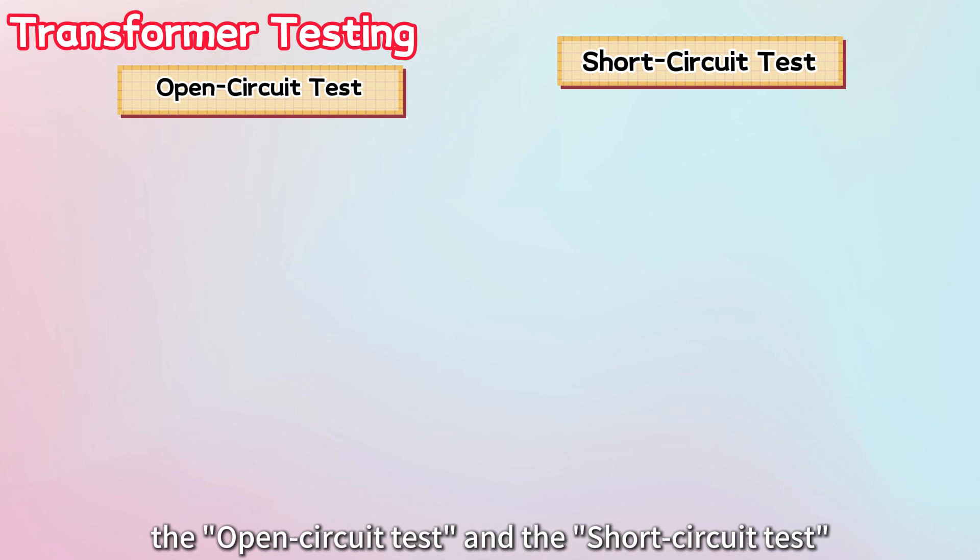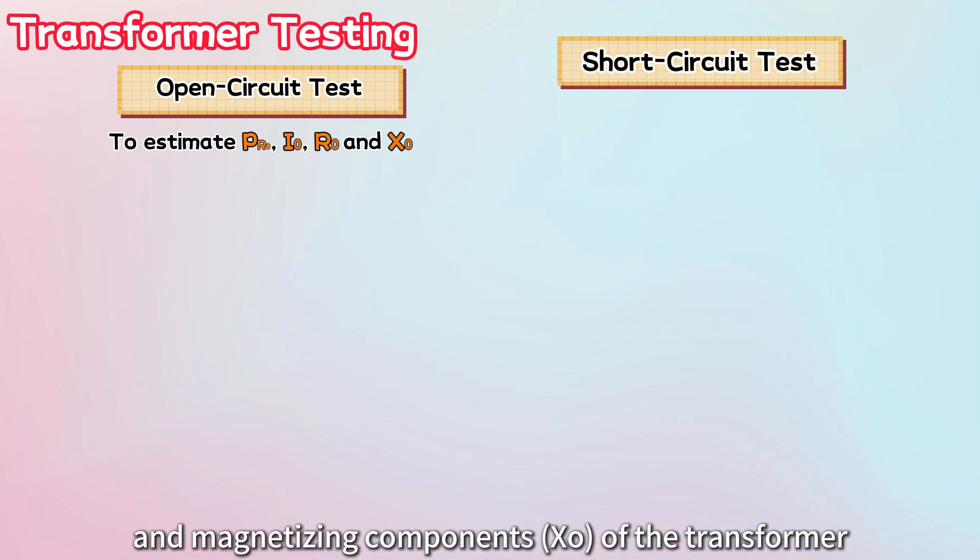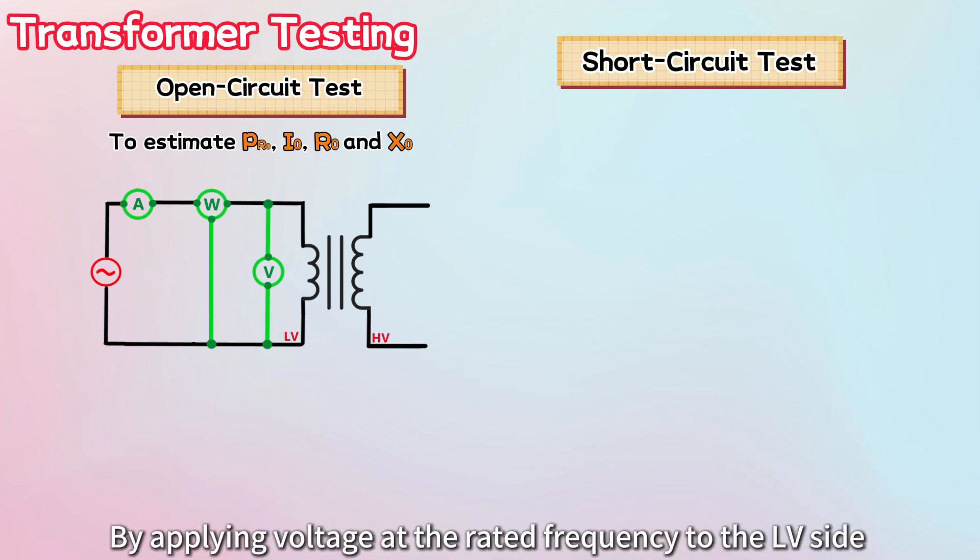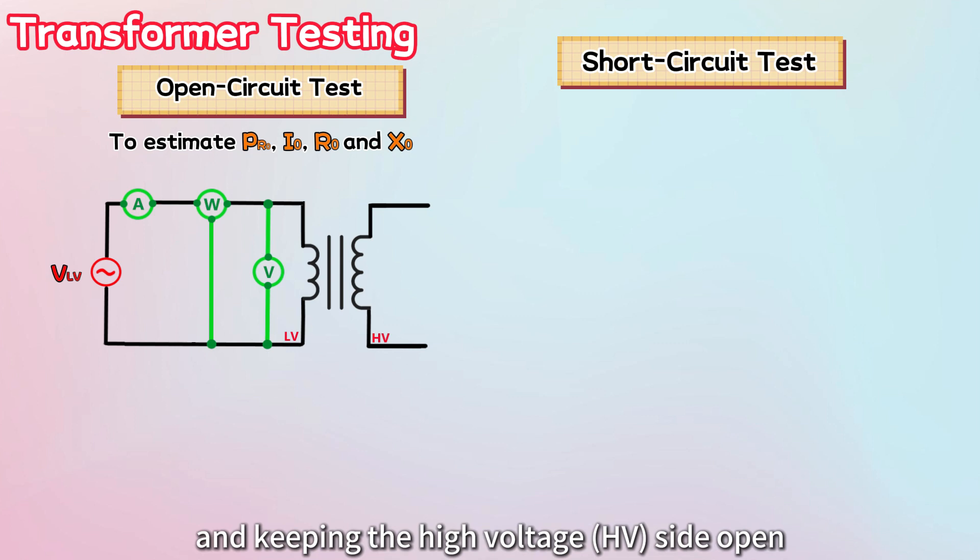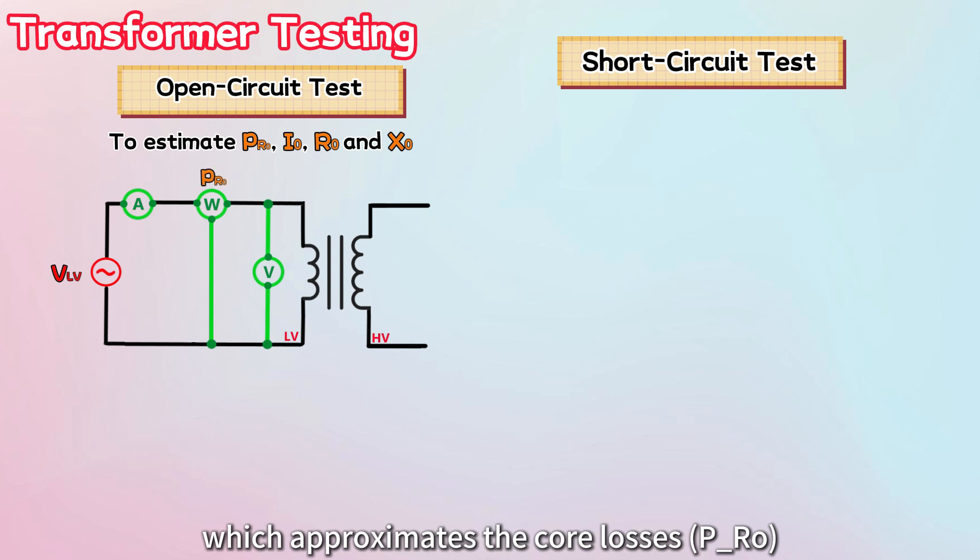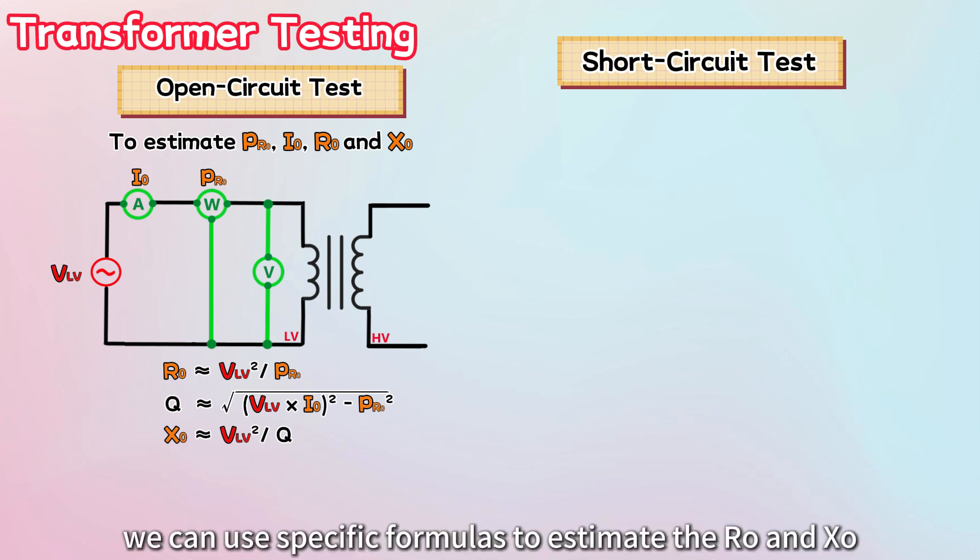Finally, let's discuss two essential tests that provide critical data for transformers: the open-circuit test and the short-circuit test. First, the open-circuit test determines the no-load losses, which are the core losses, no-load currents, core loss component R0, and magnetizing component X0 of the transformer. In this test, a voltmeter, wattmeter, and ammeter are connected to the low-voltage side of the transformer. By applying voltage at the rated frequency to the LV side and keeping the high-voltage side open, we can measure the input power with the wattmeter, which approximates the core losses. The no-load current is indicated by the ammeter. After that, we can use specific formulas to estimate R0 and X0.